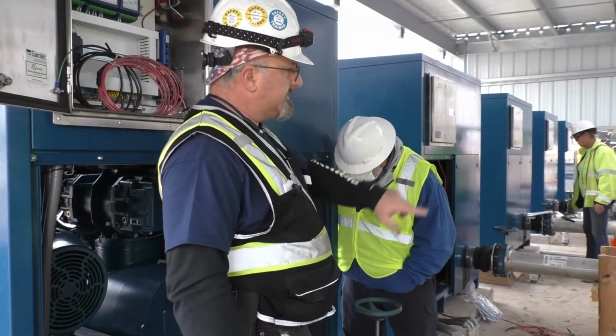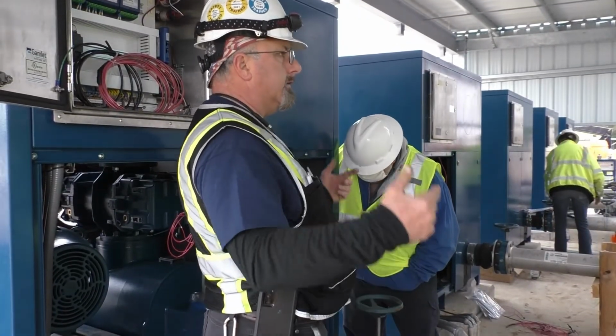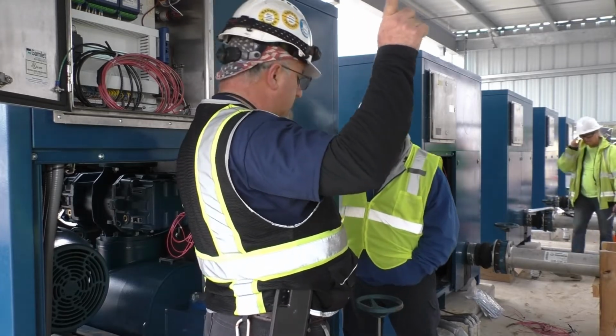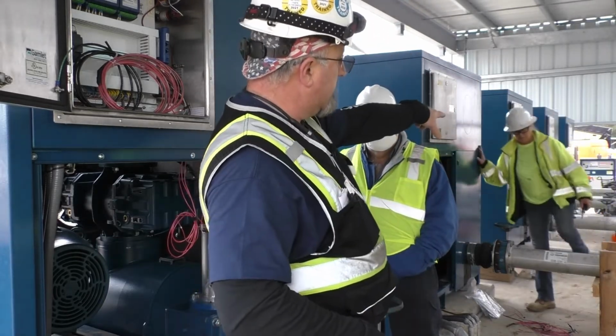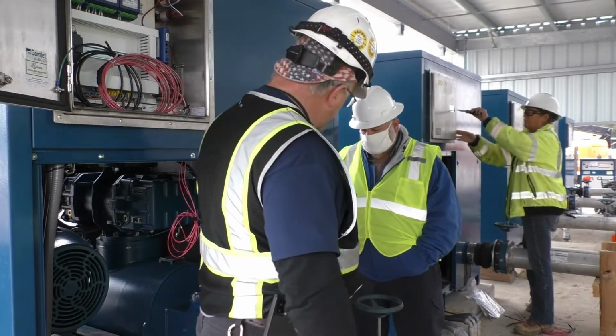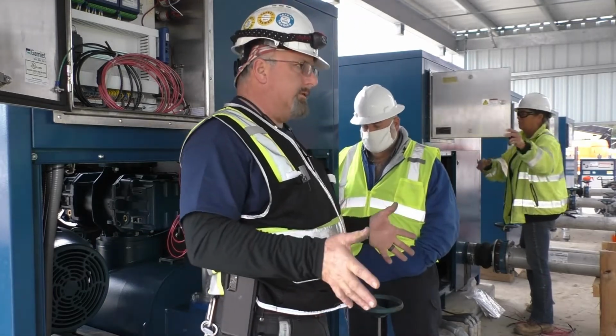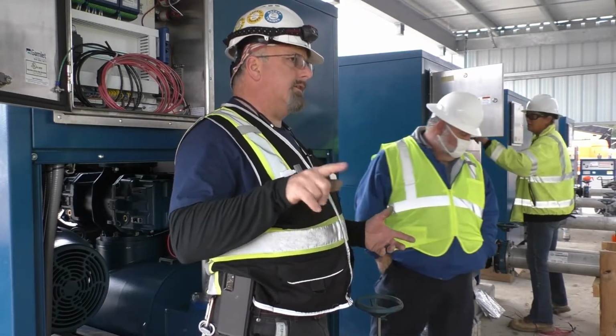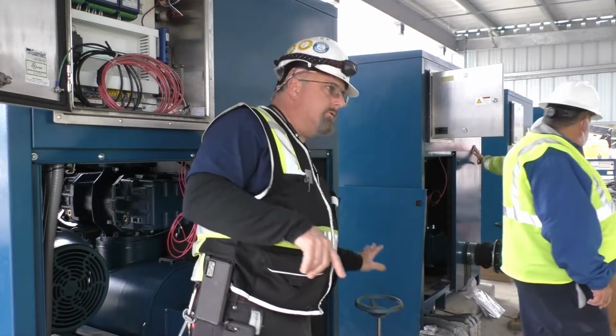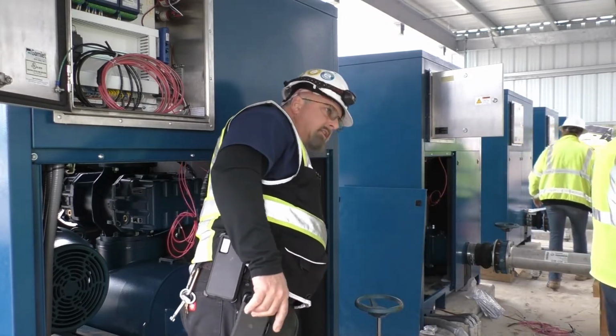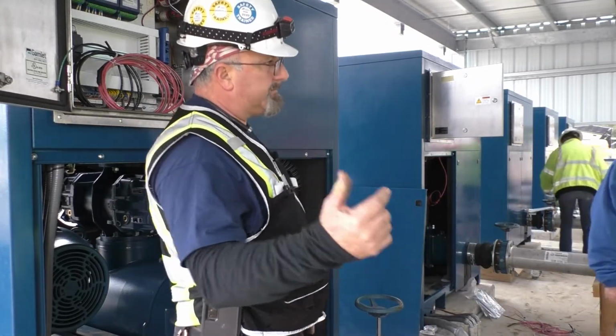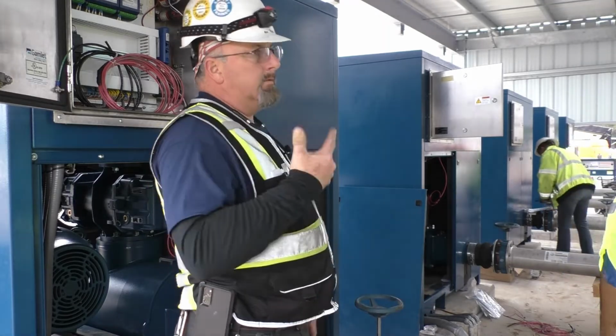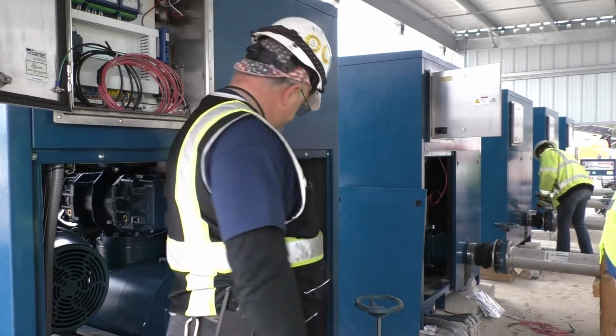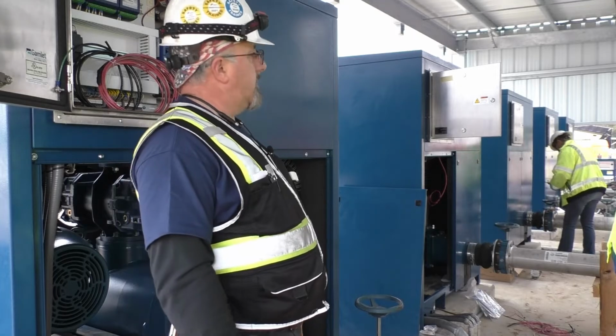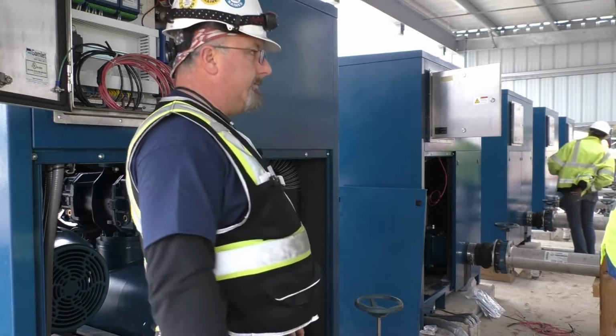I don't know if these 2 blowers in particular have a common header up top, but those have a common header. If you were to come out and a blower that was off, you could hear it turning, you probably want to come shut this and check that, because that means it's probably getting backflow into it, which is causing it to turn backwards. And do we want them to turn backwards? No. That's a very bad thing.